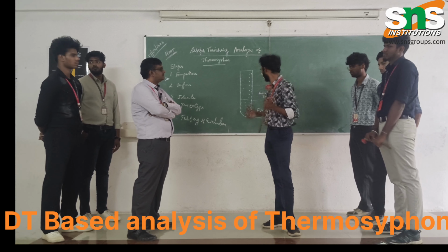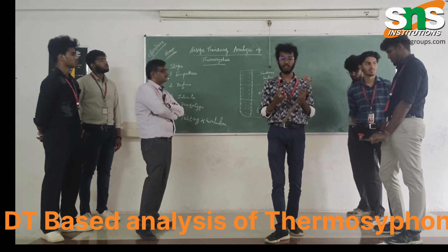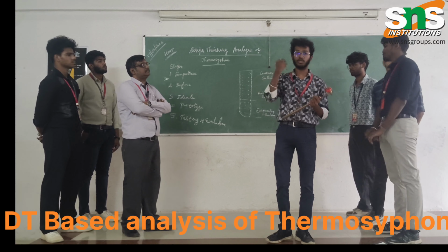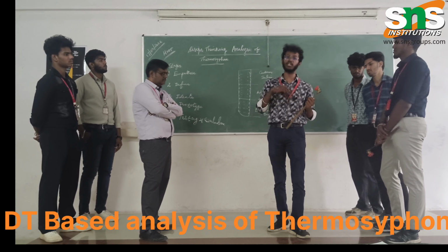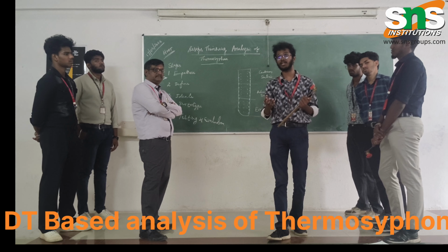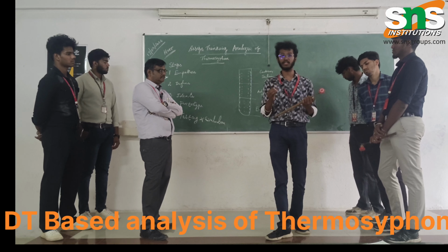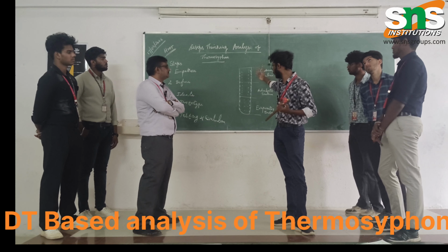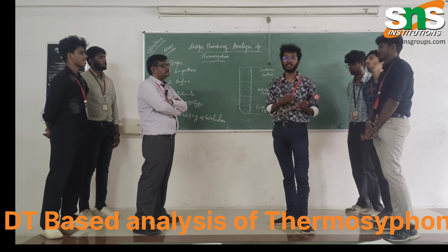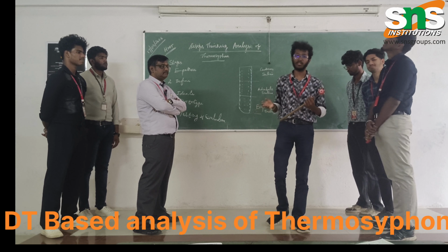Then it goes to the adiabatic section, and then it goes to the condenser. In the condenser, the gas form is transformed into the liquid form because the heat is removed there. After that, the liquid flows downwards due to gravitational force. This is the process of how the thermosyphon works.